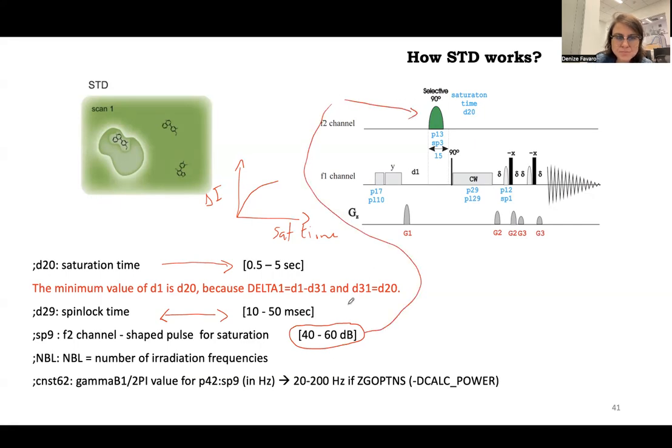But you set the power. You can either choose the power, for example, between 40 and 60. So 60, you have really weak saturation and 40 is strong saturation. You want to be selective. You want to just selectively excite the protein peak. You can also, there is on this pulse sequence, you can do minus calc power. So then instead of choosing the power, you can choose. I want to excite 20 Hertz, 100 Hertz, 200 Hertz. Again, you want to be selective. So you won't go beyond 200 Hertz, but you want to also excite a reasonable region of your protein.